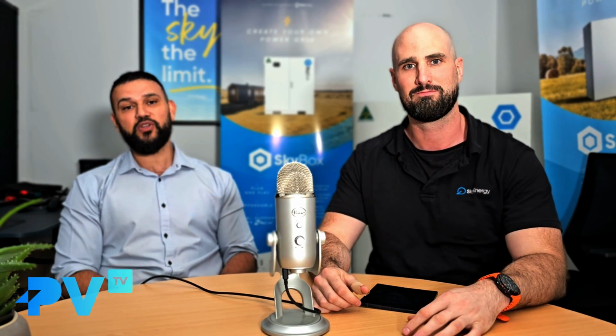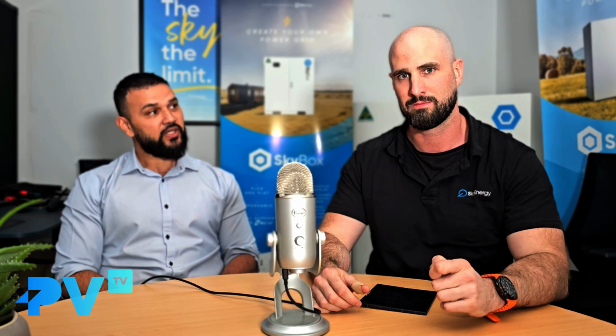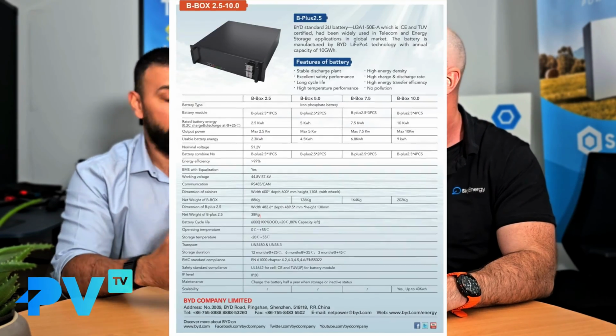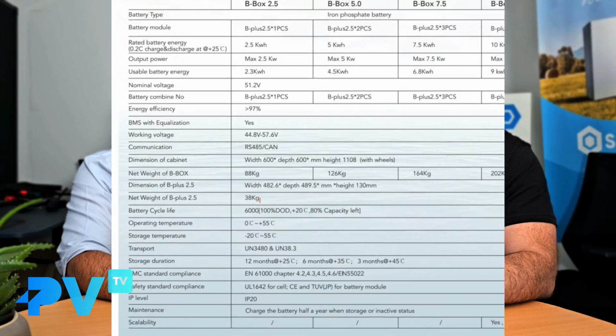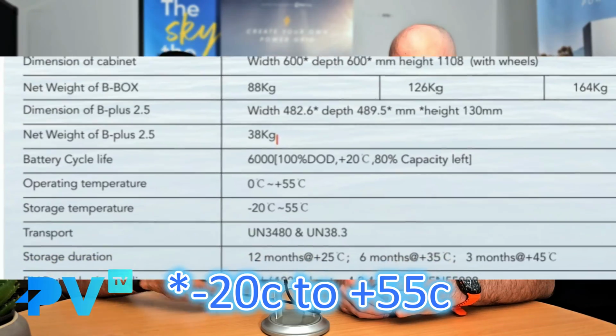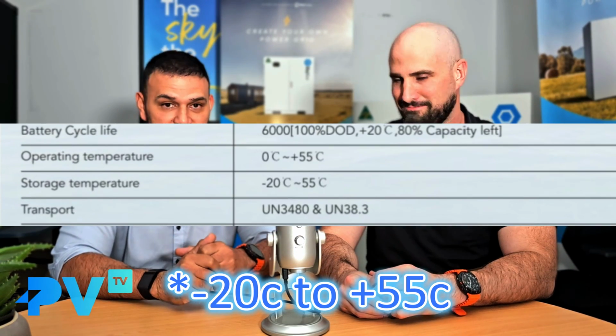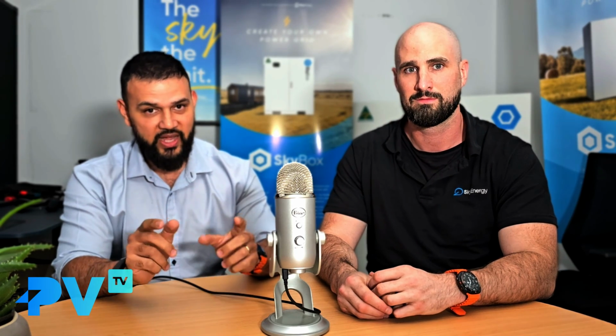Operating temperatures is a good one because the data sheets for a lot of batteries, especially lithium batteries, can be a little bit confusing, borderline deceptive in a way. Let's take a BYD battery for example, which is a very popular battery. An operating range might say -20 degrees to +65 degrees. That's a pretty wide range - you think, you beauty, that should be good. But what actually happens is the charging and the discharging have two different operating ranges as well.